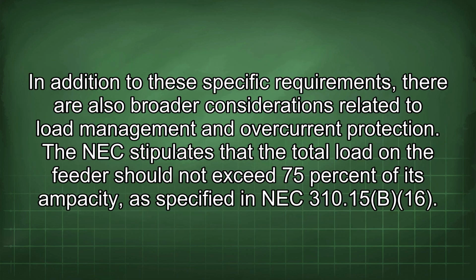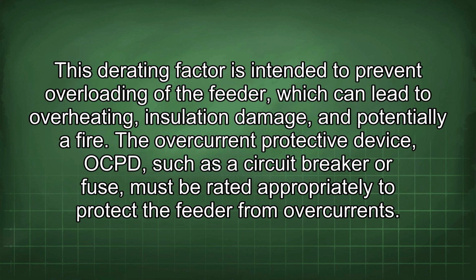In addition to these specific requirements, there are also other considerations related to load management and overcurrent protection. The NEC stipulates that the total load on the feeder should not exceed 75% of its ampacity, as specified in NEC 310.15(B)(16).